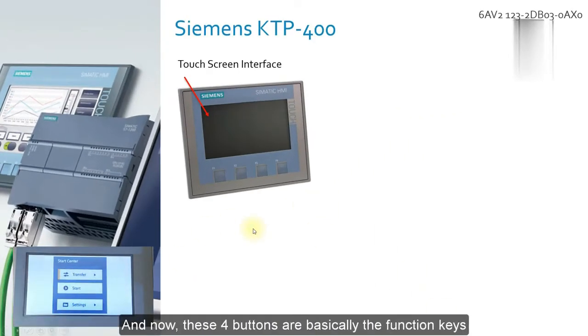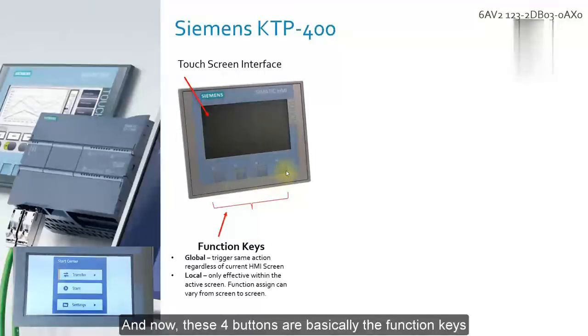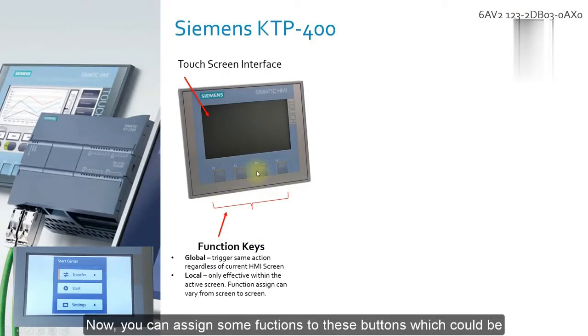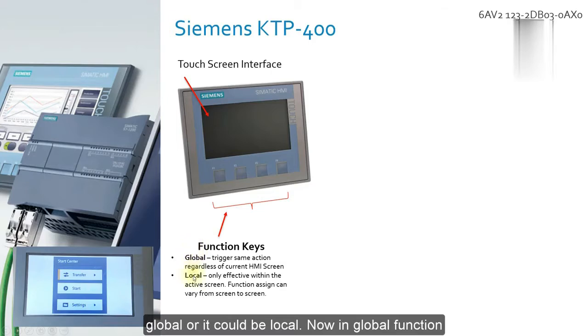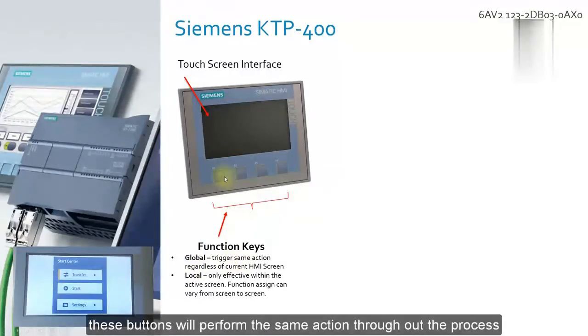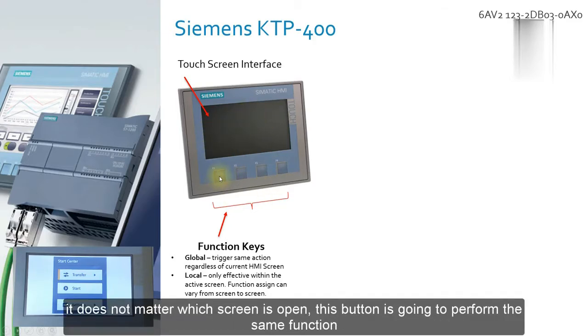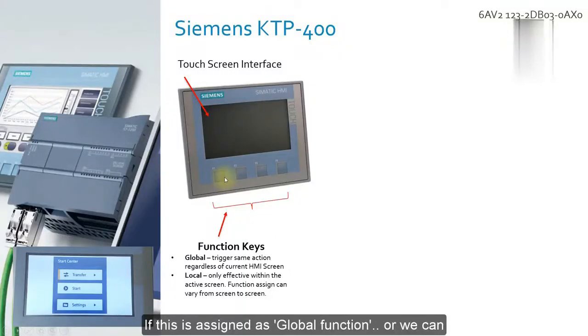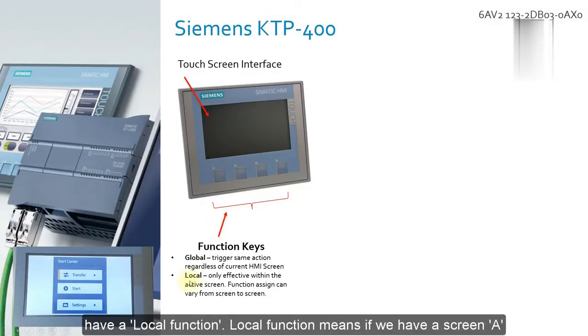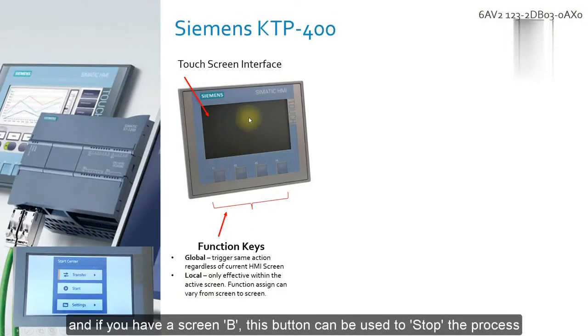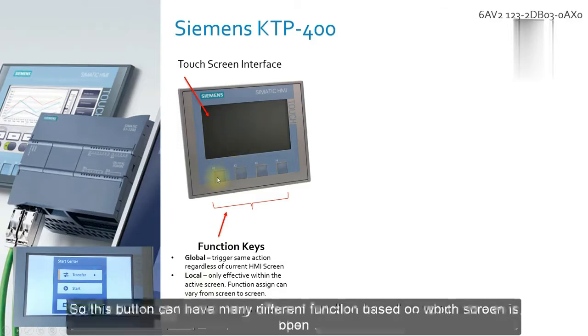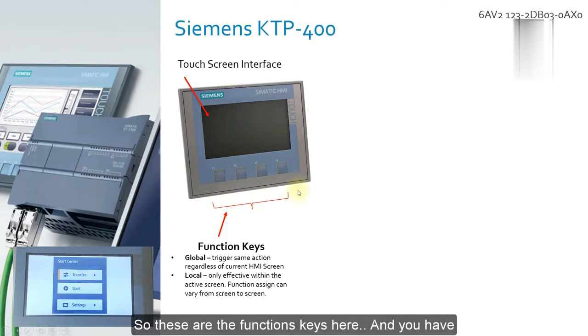These 4 buttons are basically the function keys. You can assign some function to these buttons, which could be global or local. With a global function, these buttons perform the same action throughout the process. It doesn't matter which screen is open, the button performs the same function if it is assigned as a global function. Or you can have a local function. Local function means if you have a screen A, let's say, this button could be used to start a process, and if you have a screen B, this button can be used to stop the process. So this button can have many different functions based on which screen is open. These are the function keys here.